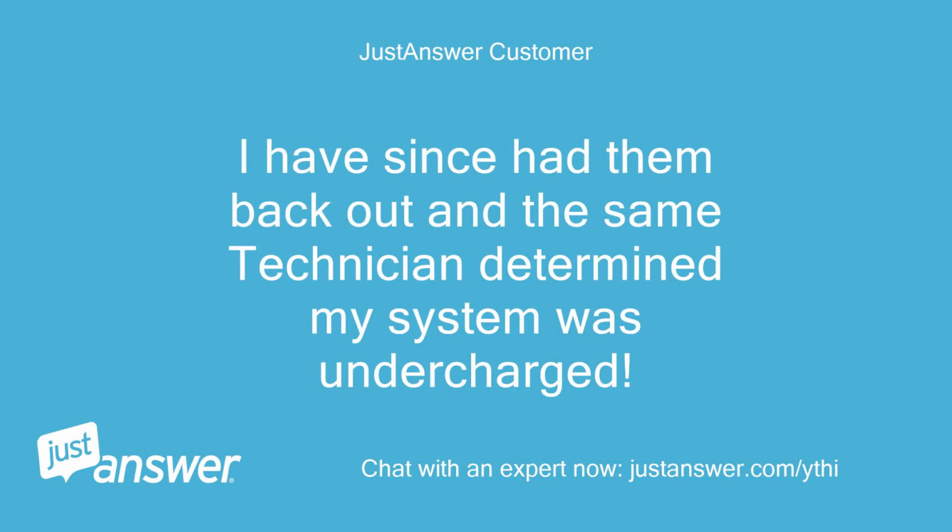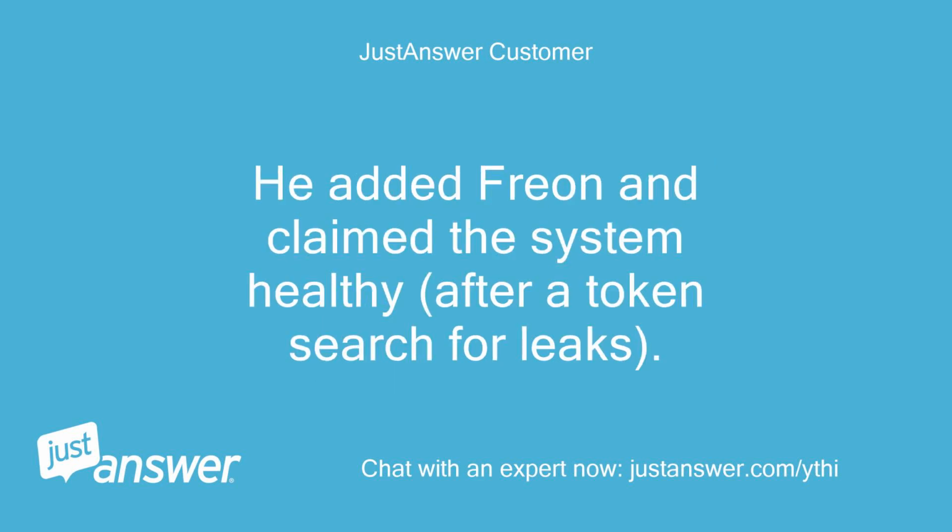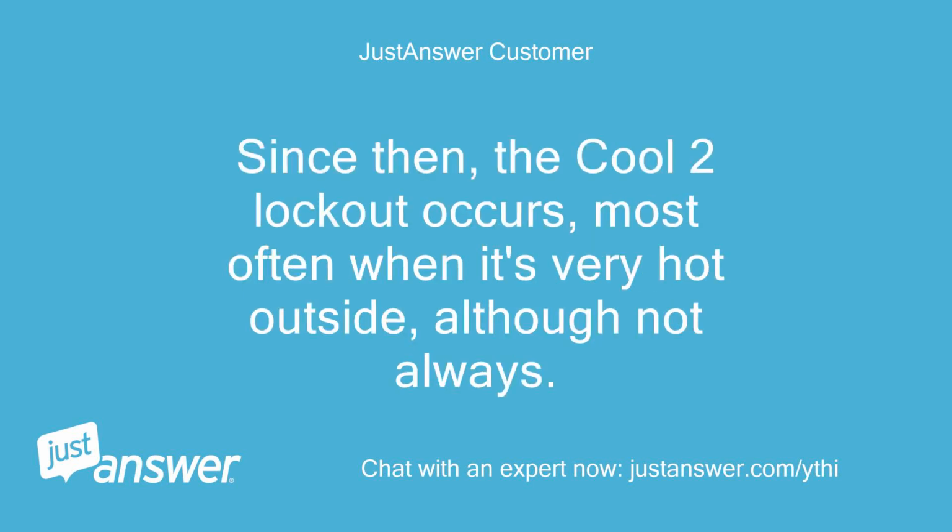I have since had them back out, and the same technician determined my system was undercharged. He added Freon and claimed the system healthy, after a token search for leaks. Since then, the cool 2 lockout occurs, most often when it's very hot outside, although not always.